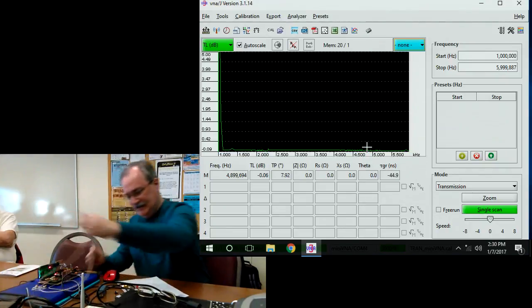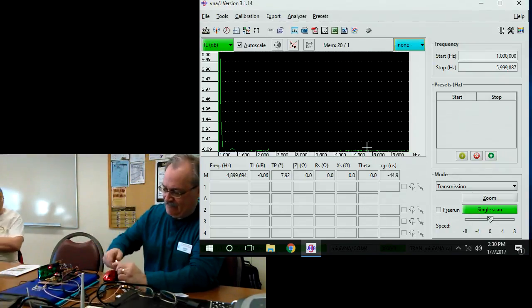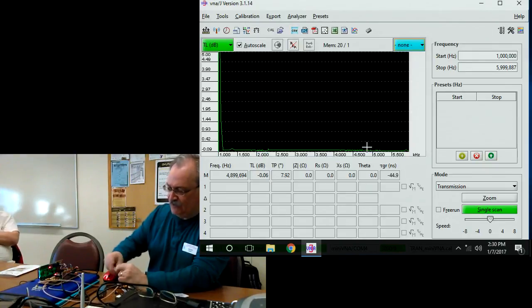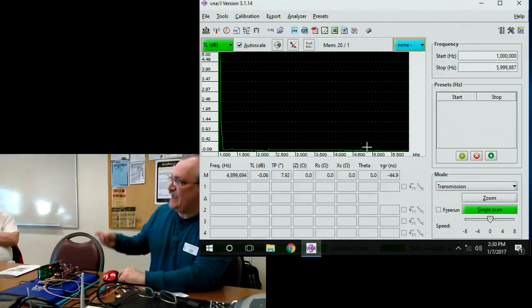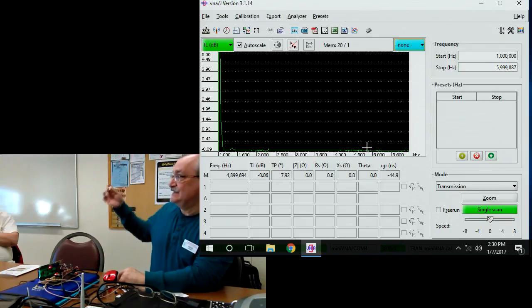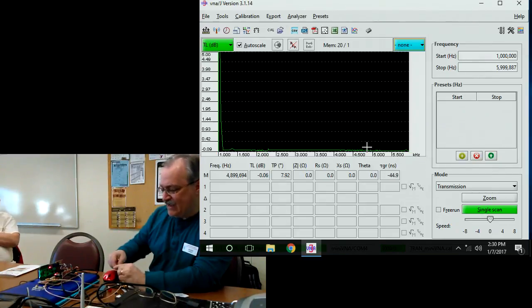If I put an attenuator in the middle of it, a good test for an instrument of this caliber is if I have a known attenuator that I've characterized with much better equipment, and it's come with a certificate of calibration, which this did. I have a measurement, not so much a transfer standard, but I have something to compare against. And actually this comes very close to where it should if you had spent a great deal more money. Add 4 or 5 more zeros to what something like this cost to get a VNA.